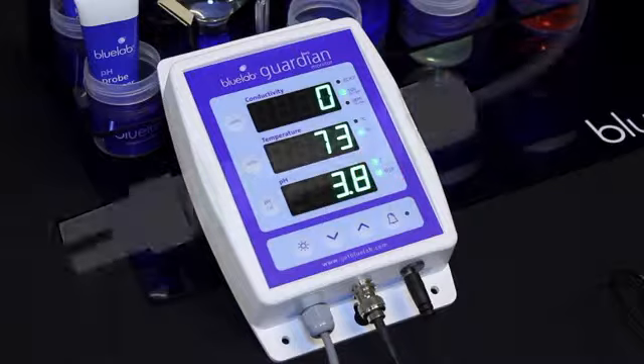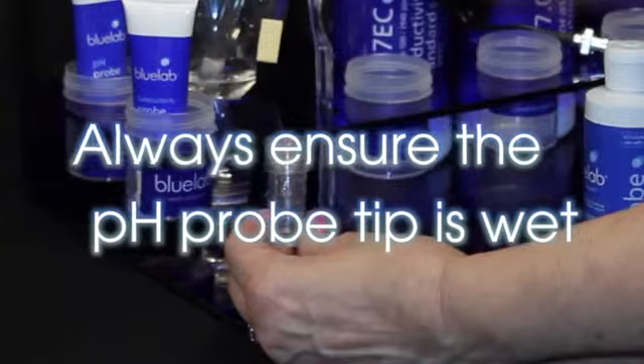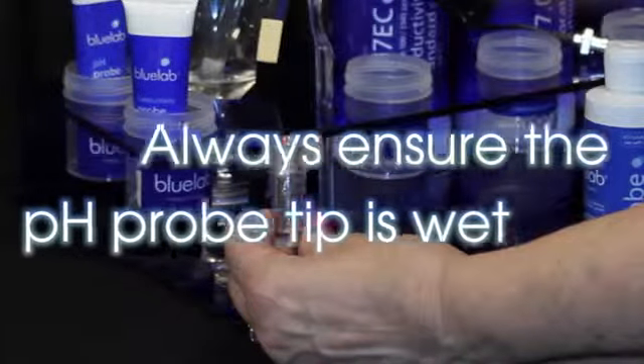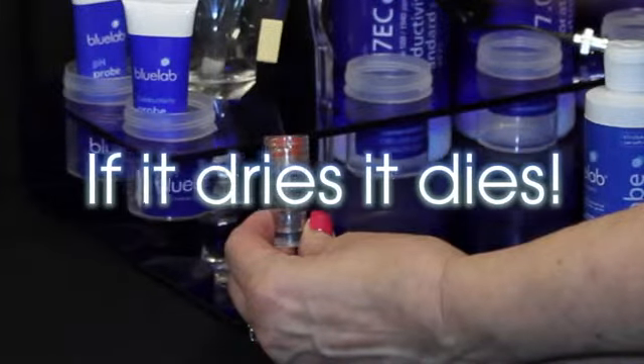The calibration indicators will flash or disappear 1 month after the last successful calibration to remind you it's time to calibrate again. Your conductivity temperature probe is factory calibrated, so it is ready to use. You'll need to clean and test it once a month to ensure accurate readings. To store the pH probe when not in use, always ensure the pH probe tip is wet. If it dries, it dies.